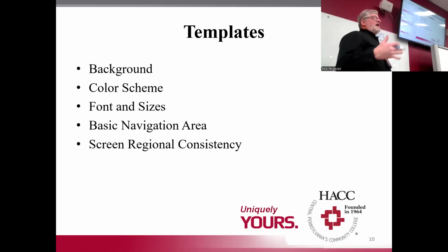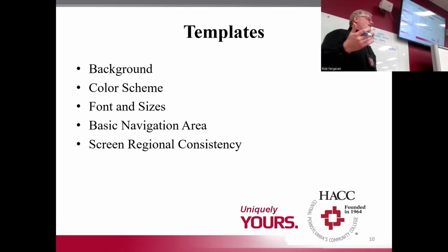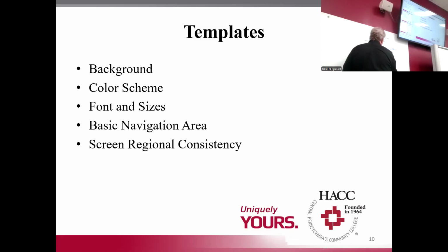Third, you've got to come up with fonts. You're going to limit yourself to maybe 2 sizes, maybe 3 sizes of fonts. So you're going to stick to a common font and you won't have more than 2 to 3 sizes. You're also going to stick to a navigation area. Generally speaking, I like the bottom of the screen for navigation. When I used to build HMIs, I would have my navigation buttons down here.